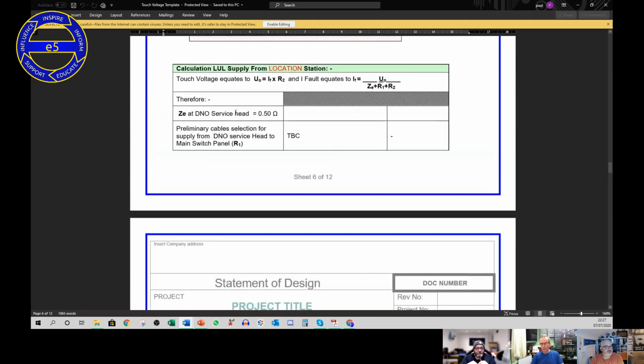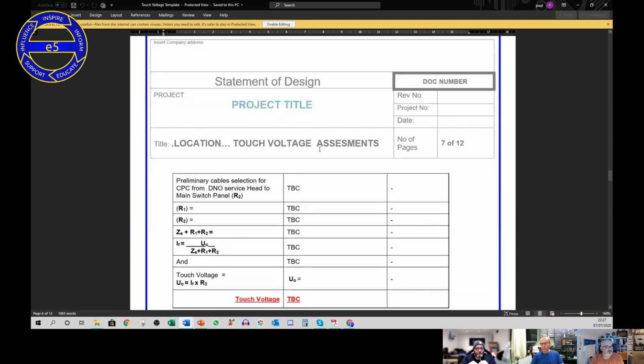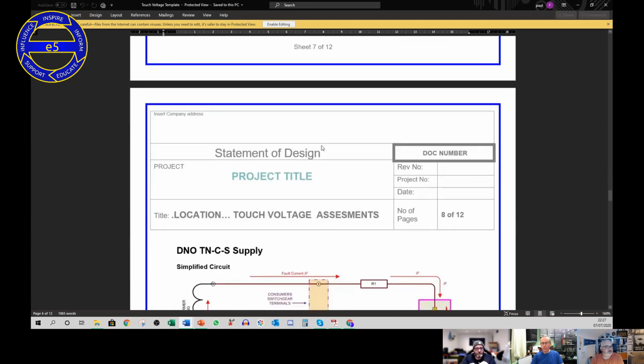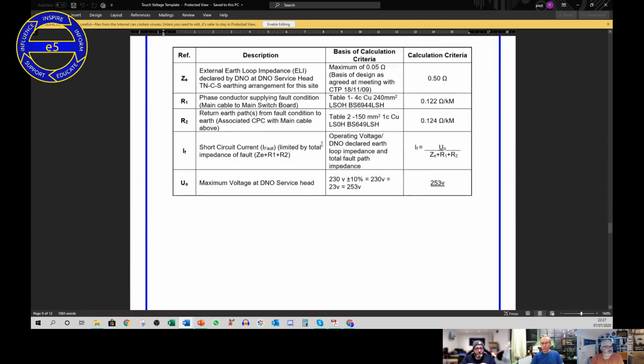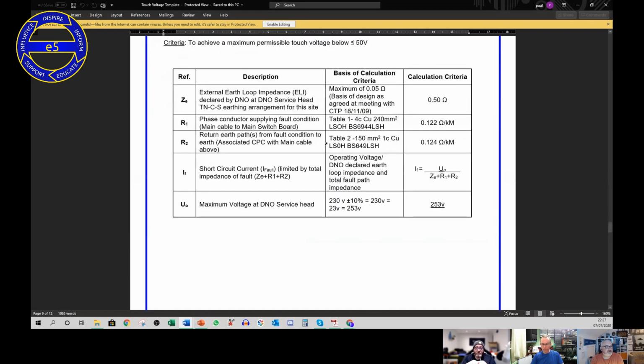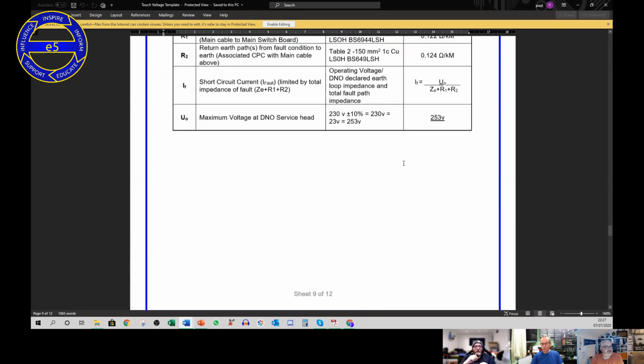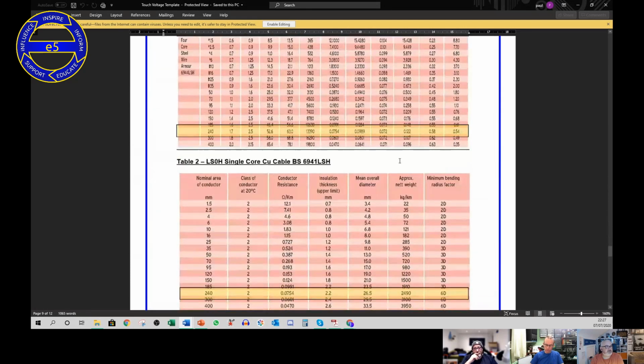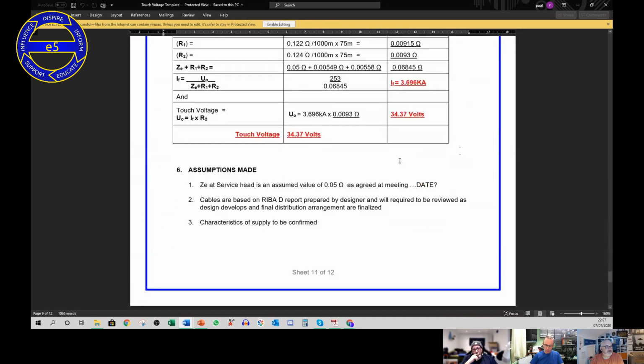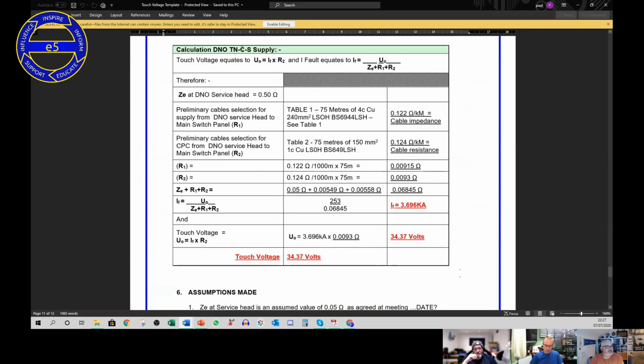So we had the measurement at the service head, and if you go all the way down, because we worked it out for each type, there you go, maximum voltage at the service head, what all the resistance values were, to the point where we got all the way down. So that was on a TNCS supply, touch voltage equated to a maximum of 34.37 volts.